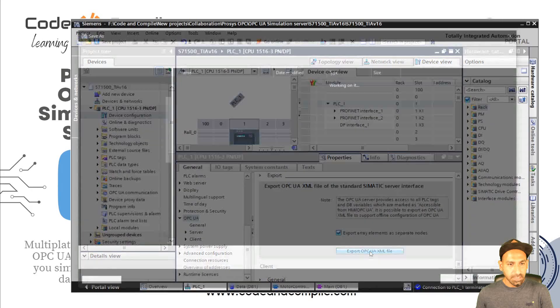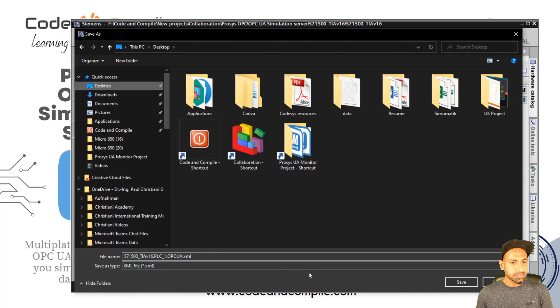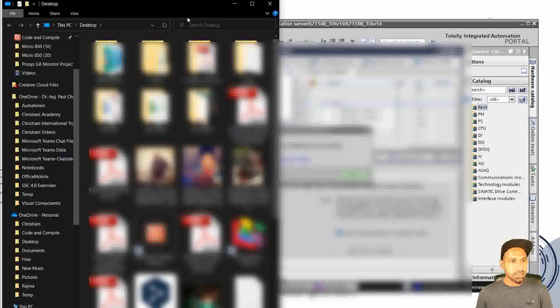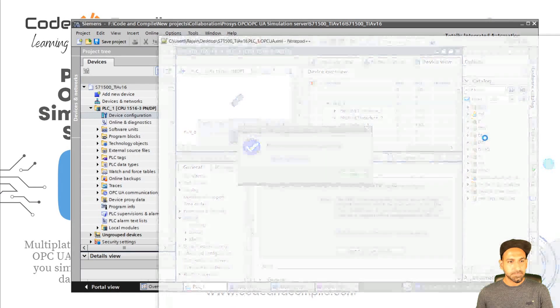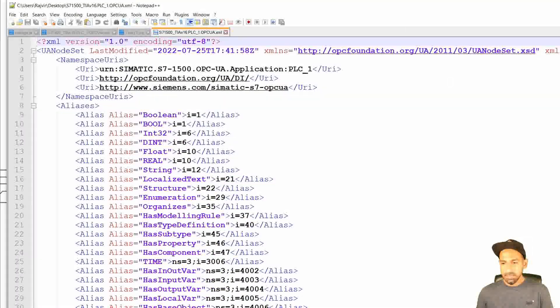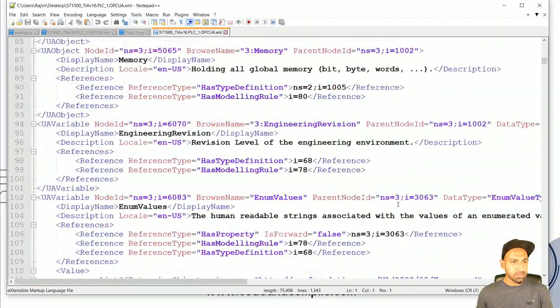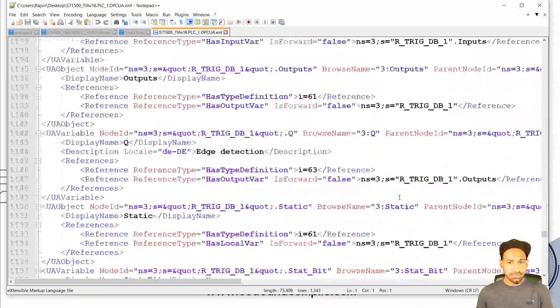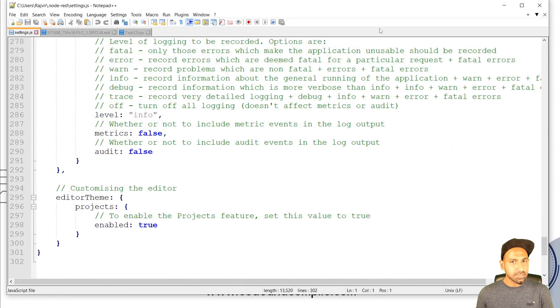In Siemens PLC it's very easy because of their amazing feature — you can export your OPC UA model. Go to the PLC properties, then OPC UA, and scroll all the way down to find 'Export OPC UA XML file'. Click it, choose a location like the desktop, and click Save. The file is now exported. If you open it in Notepad, you'll see it's an XML file exported from TIA Portal, containing all OPC UA definitions — types and tags — everything defined. You just export it to your desktop.